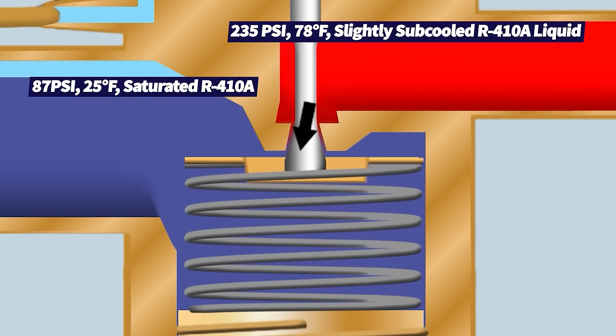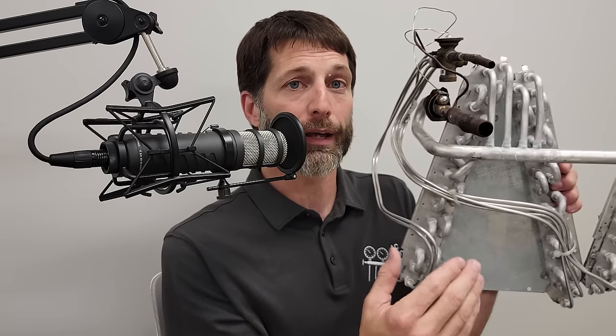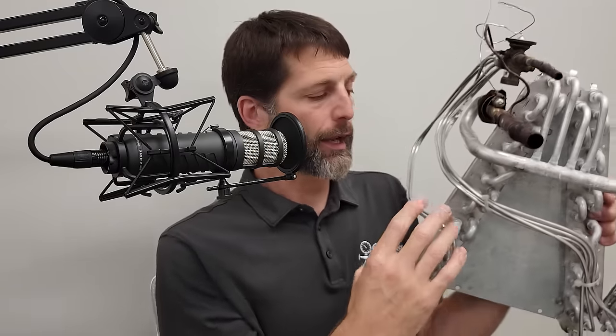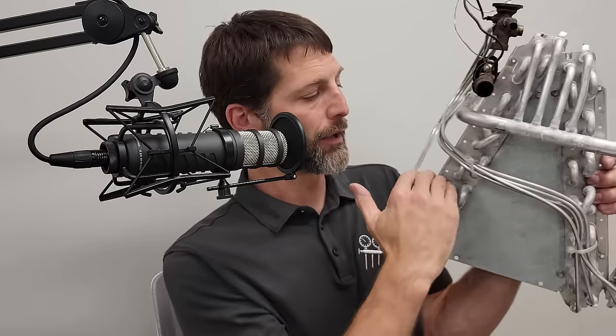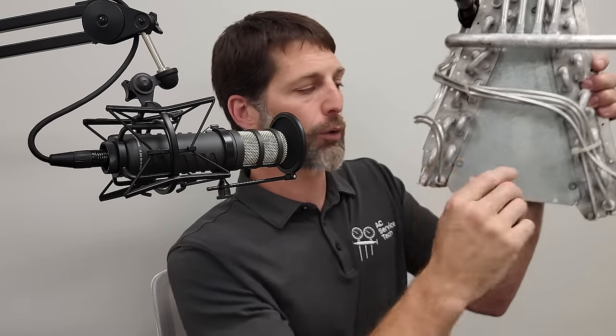When you have a liquid line restriction, the refrigerant is too low in pressure, which means it's too low in temperature. But you'll notice only the lower part of the coil will freeze, because you're going to have high superheat and it will be melted basically in the upper part. It's only going to be frozen in the lower parts where the distributor tubes are entering — that's a telltale sign of a liquid line restriction.